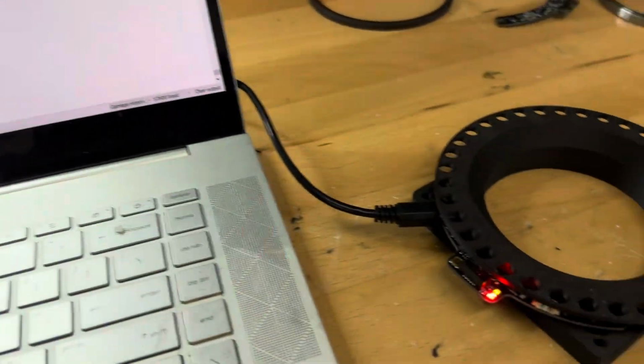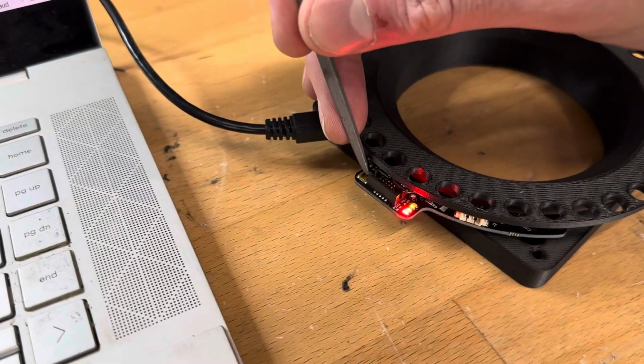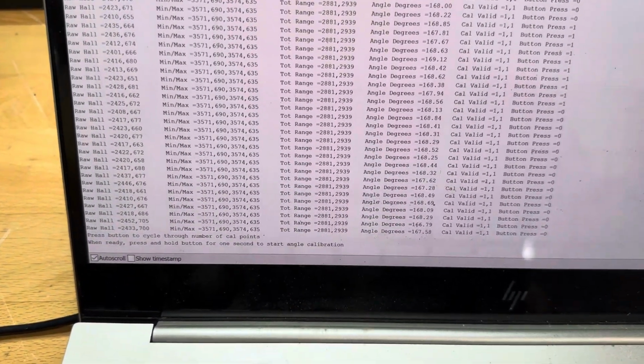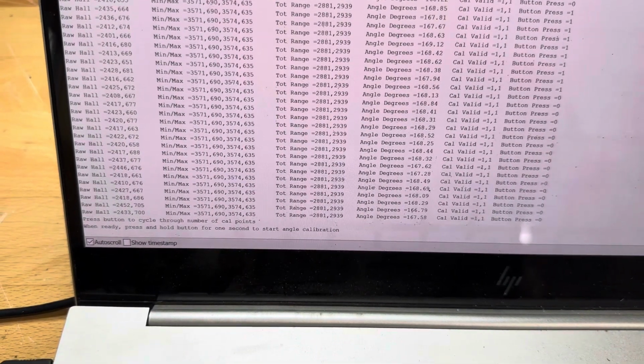Okay, now I've got the valid signal. Everything's happy, I've got a min-max. I could go to basic calibration, click the button once, and the sensor would start working. I wanna do advanced calibration, so I'm gonna do button click twice. And if I do that correctly, I should get a message on the screen. Now what this is telling me is to set my number of cal points.